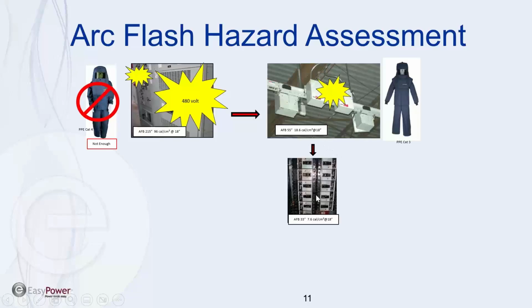So this is going to feed a breaker. We're down to a 33-inch arc flash boundary, 7.6 calories. So it's getting down there. Now all of these are going to go down once they change out that transformer. Everything downstream goes down as well. But a balaclava, shield and a hard hat.